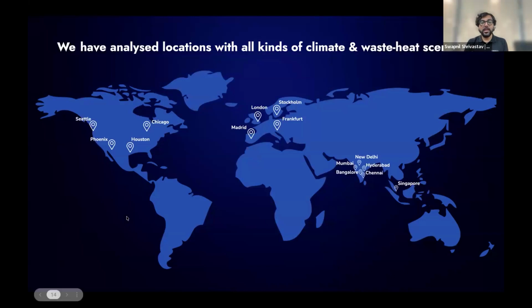And we have analyzed this with all kinds of weather and waste heat temperatures across more than 30 locations globally. In most cases, we are able to show energy reduction from your existing cooling system of 10 to 16%, as well as make about 10 to 30,000 liters per day per megawatt of water, which is then used for cooling or given back to communities.